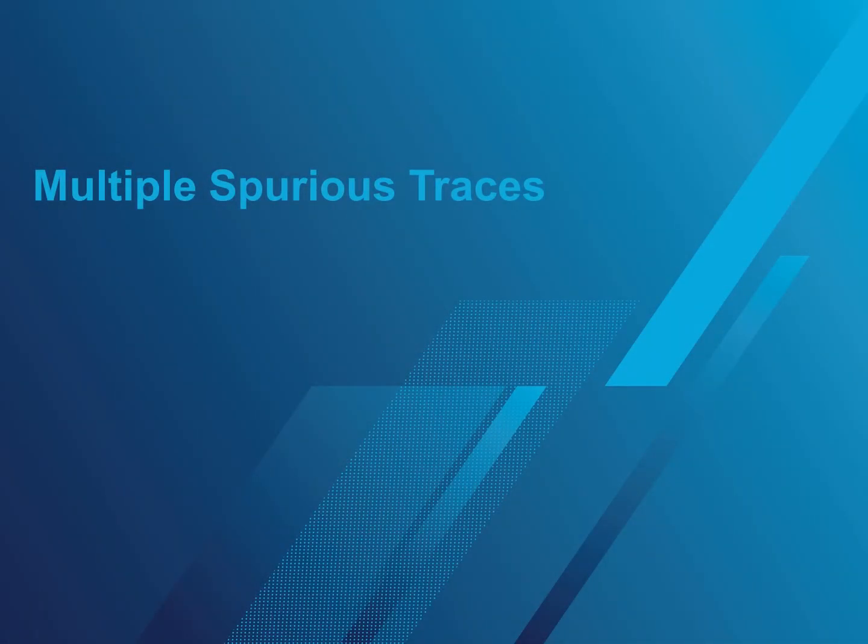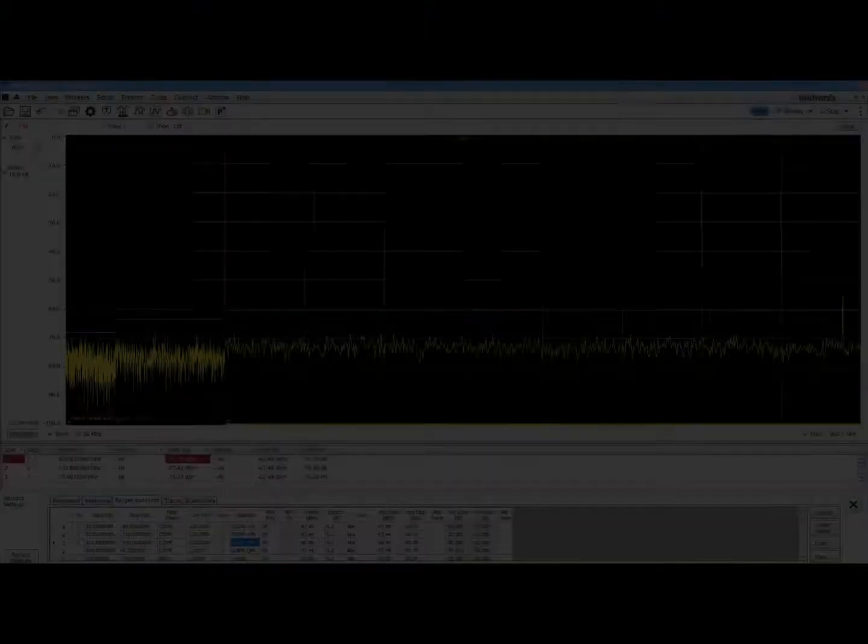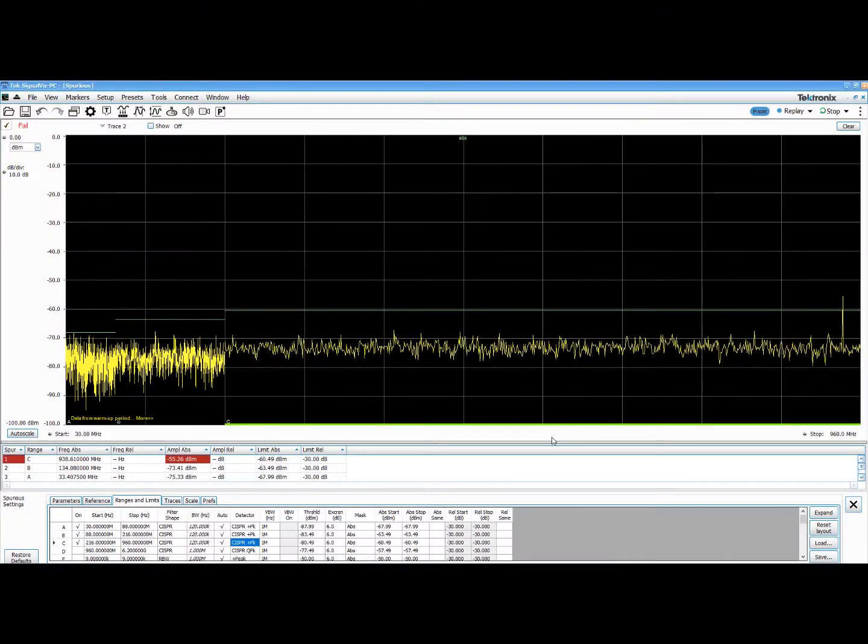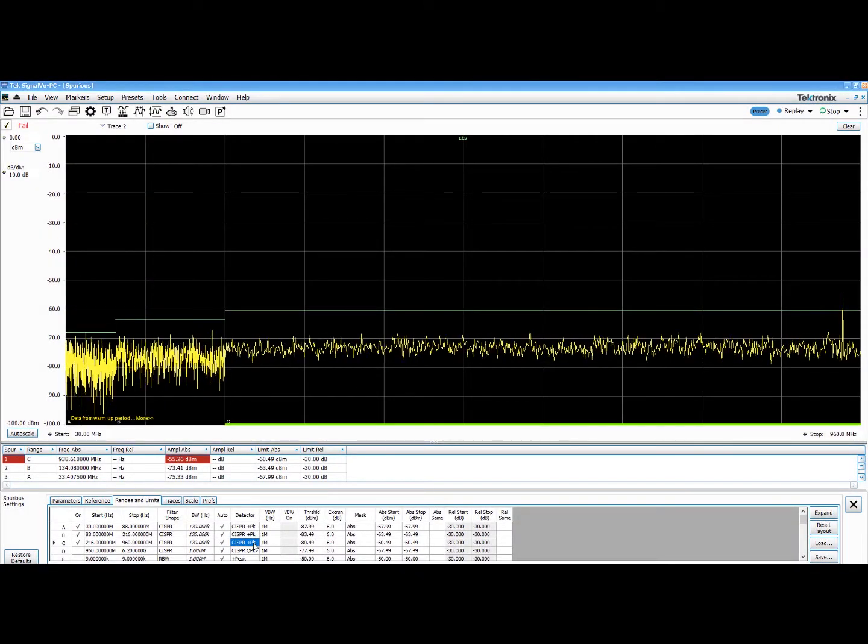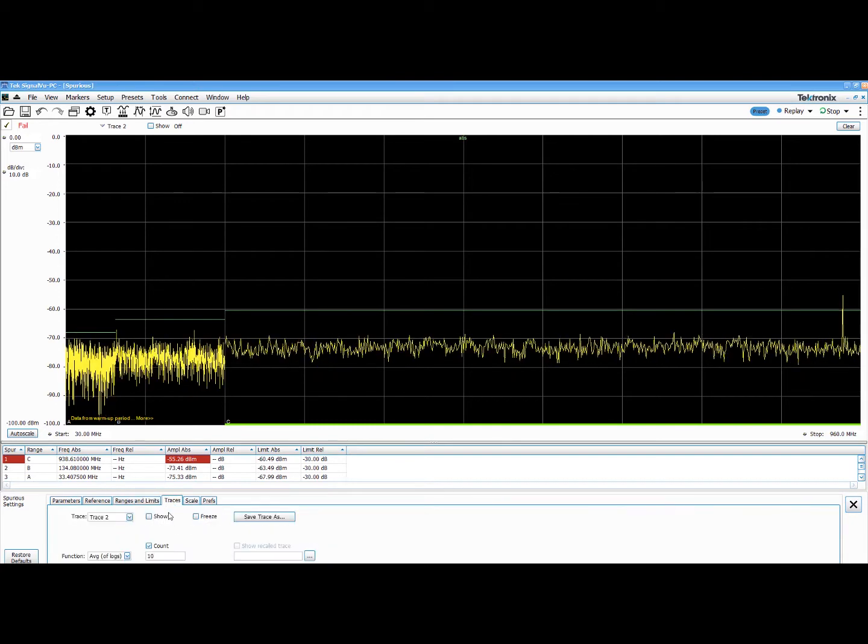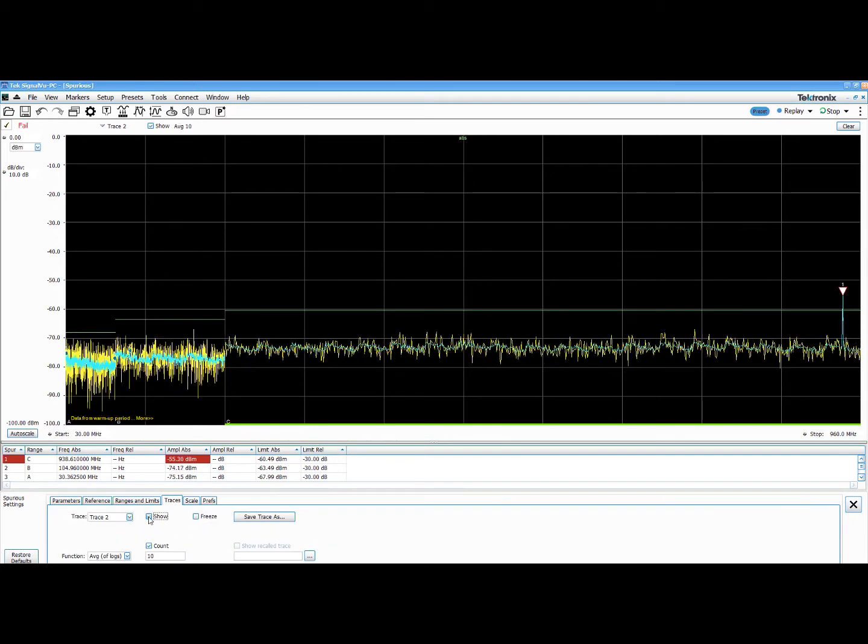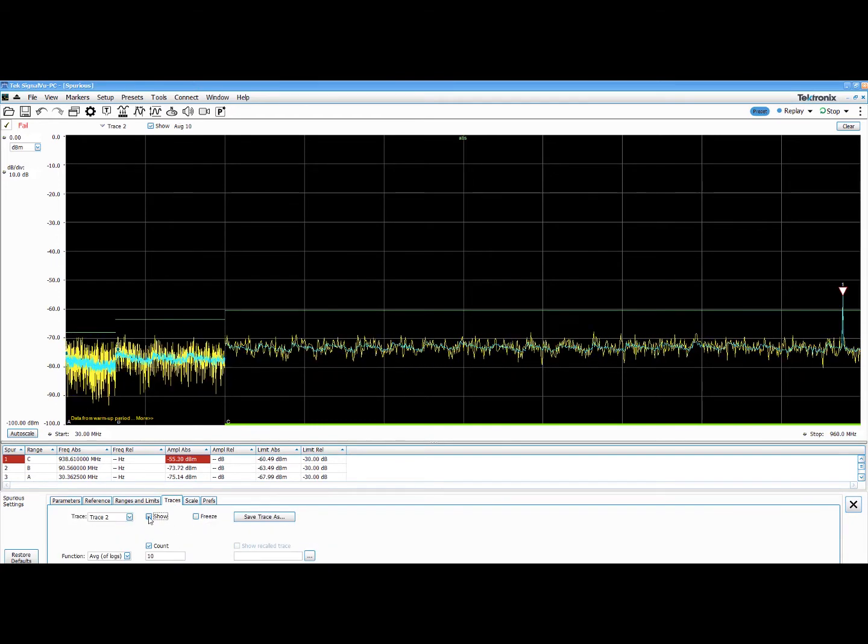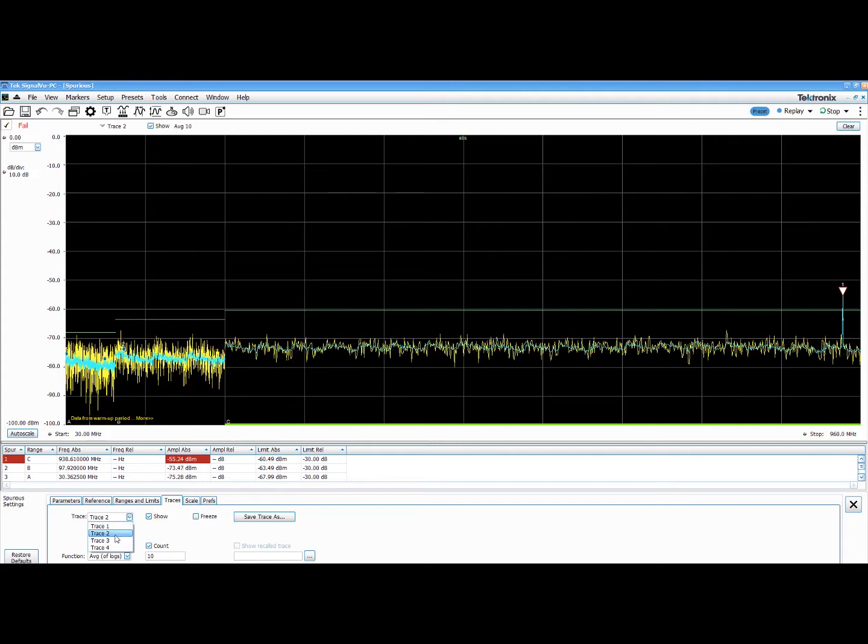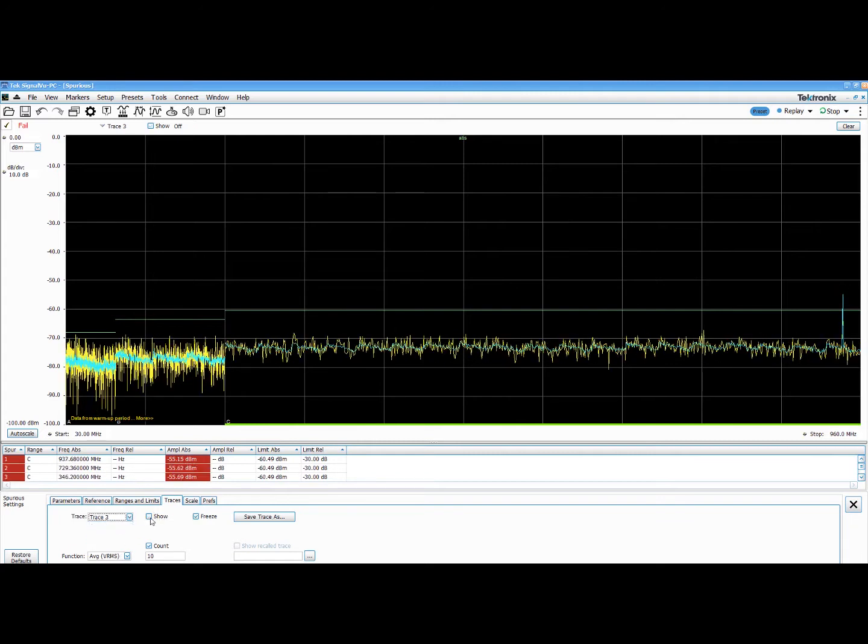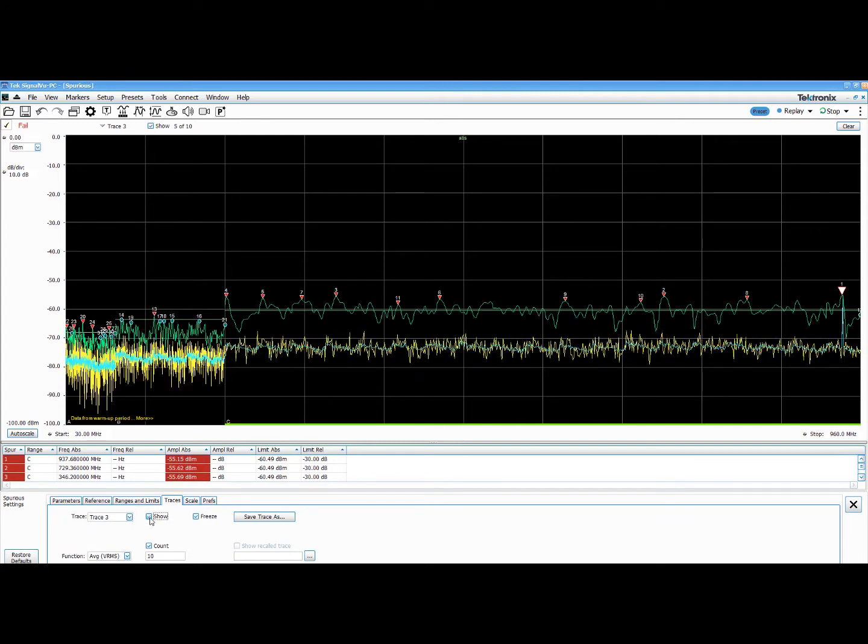Typically, during pre-compliance testing, customers often like to capture many spurious traces of a test setup, especially an ambient capture with the same setup but the DUT turned off, to identify potential interferers in the test. It is now possible to save and recall multiple traces in the spurious measurement display.